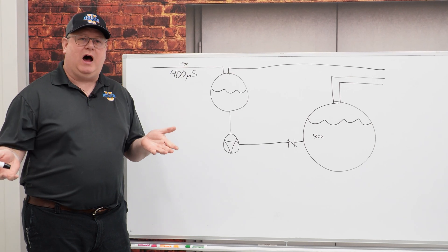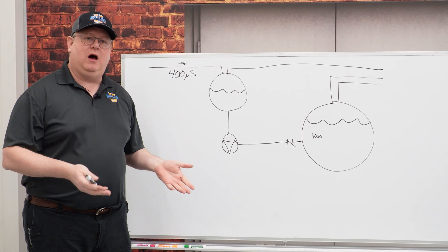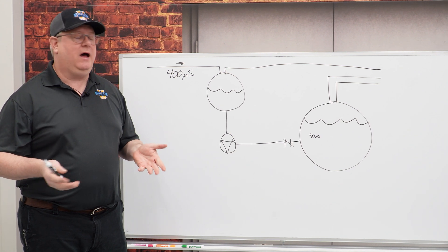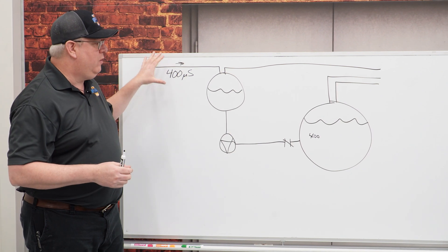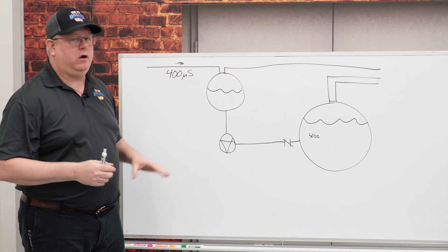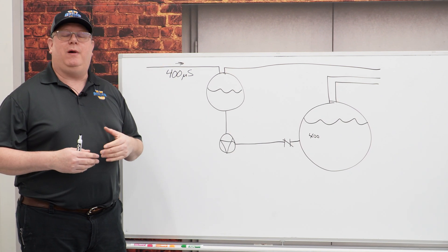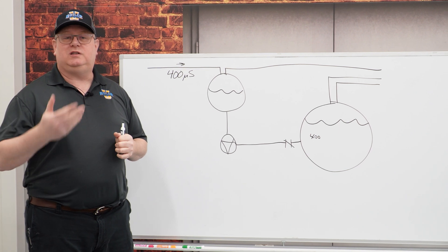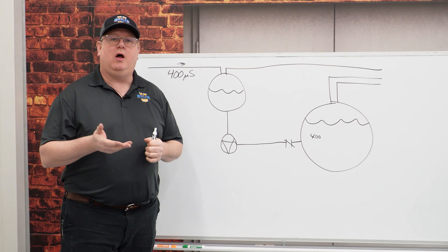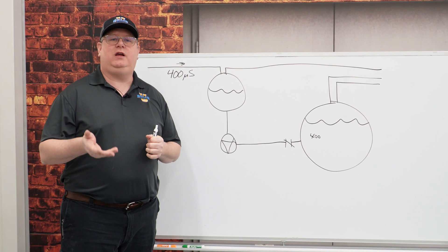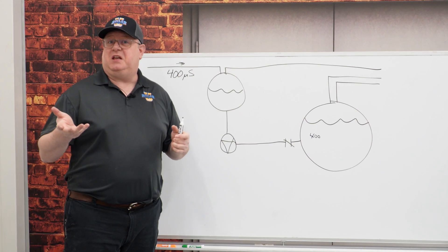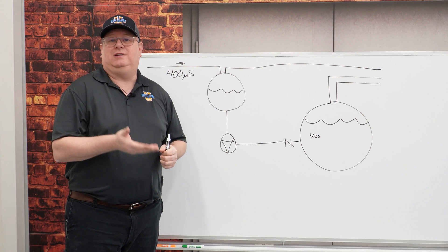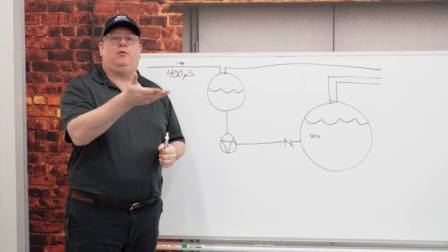Is that too high? Is it too low? Well, we really can't get any lower than that with this feed water, and it is on the low end. What's the issue with low conductivity? Nothing initially — it's just that we expect it to rise.